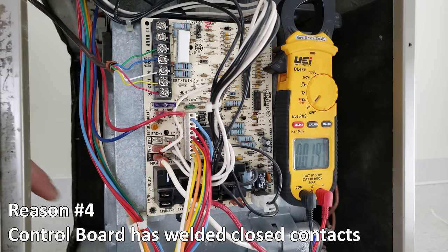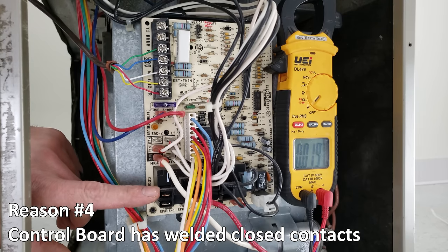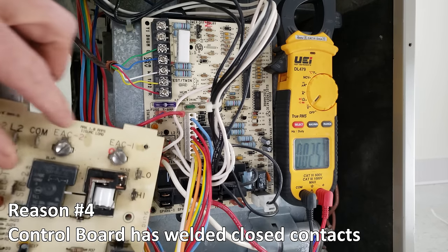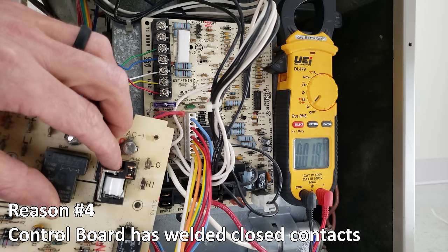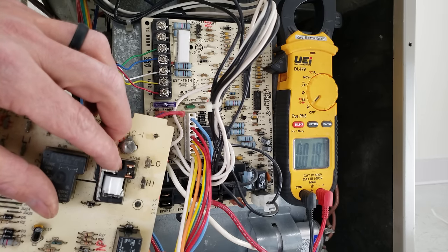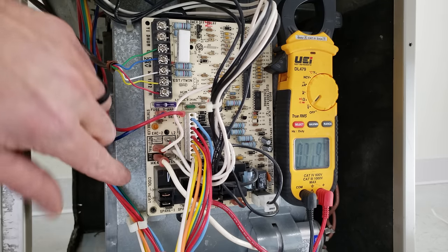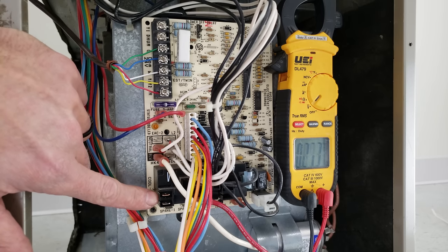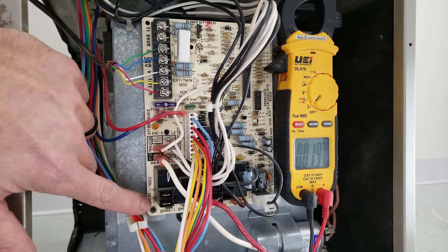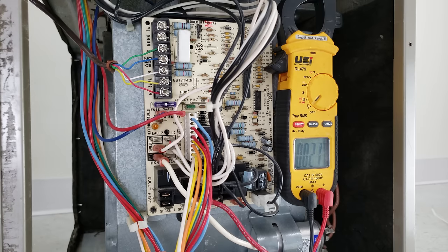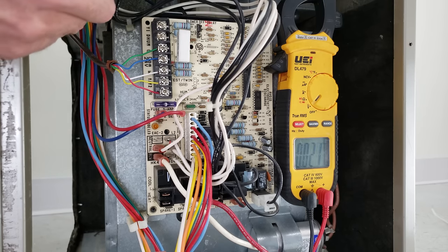Problem number four is inside this black relay right here, you could have welded shut contacts, which mean that it's always going to be allowing power to the blower motor. So this is the blower motor speed in cooling mode, and then this is in heating mode. So what I'm going to do in order to test that is turn this power on to the furnace.